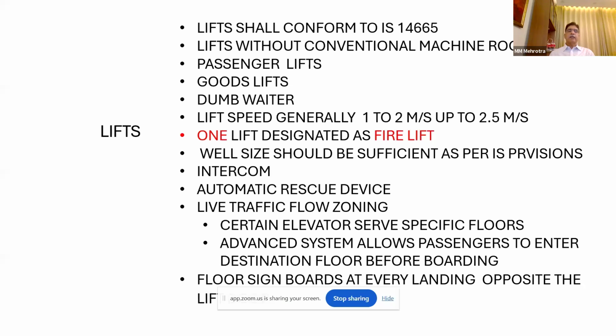Fire lift. Fire lift is important. The moment there is a fire, my fire alarm system has detected some fire, immediately my supply system to lifts will be switched off. No person in a multi-storied building should ever use a lift in case of fire. There will be only one lift which will be operational. It is known to firemen who will be entering the building from outside. So all other lifts will be made non-functional. The fire lift will be used by the firemen to reach the fire, because they know where the fire is, and whether this fire lift is safe to be used or not.